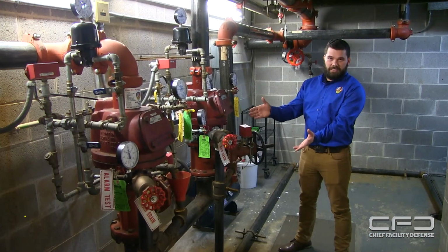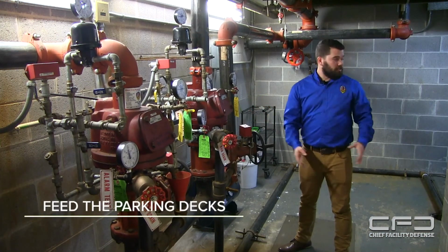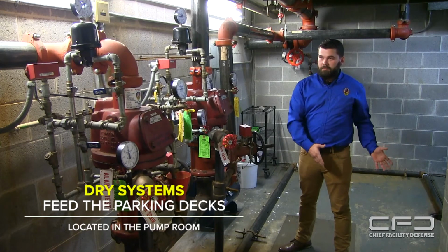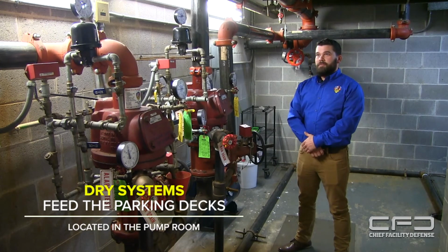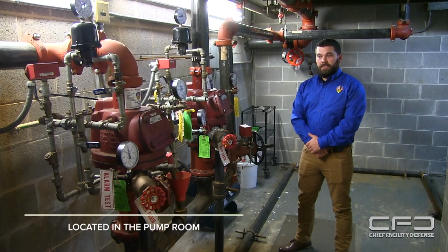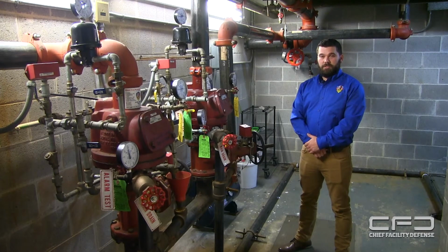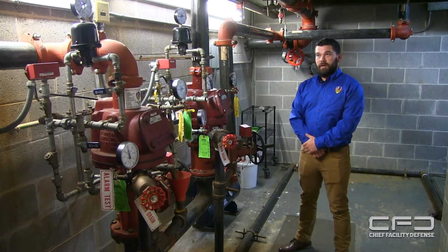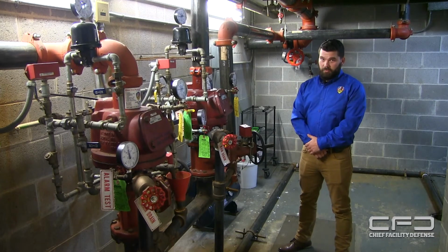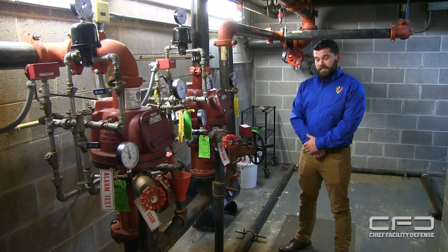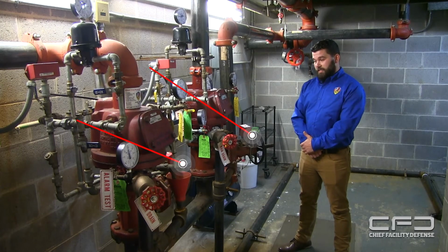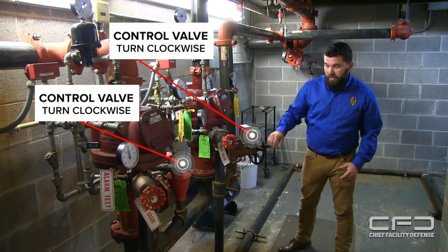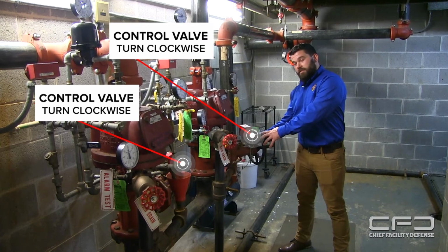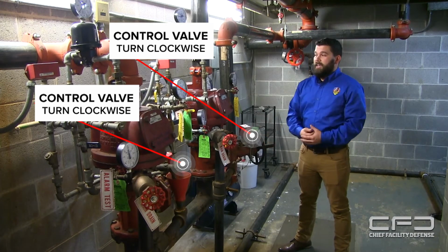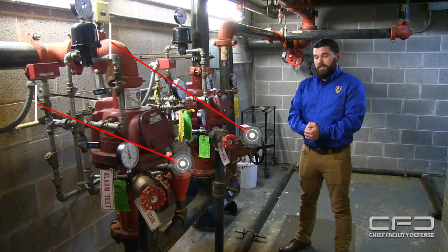Here we have your two dry systems. They feed the parking deck. They're also located in the same room as the pump here in the basement. The dry systems have air in the pipes instead of water due to freezing temperatures causing water to freeze in the pipes and burst either the couplings or the pipes, or cause a head to go off prematurely. If that's ever the case and you need to shut the water off to the dry systems, there are control valves right here at the bottom. You can turn them clockwise to shut the water supply off, and you have to call Chief Facility Defense. We will come out and reset your system.